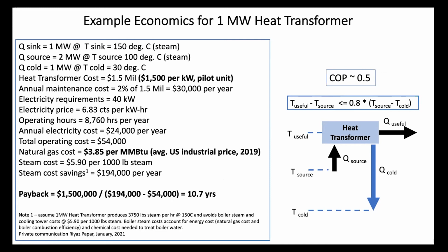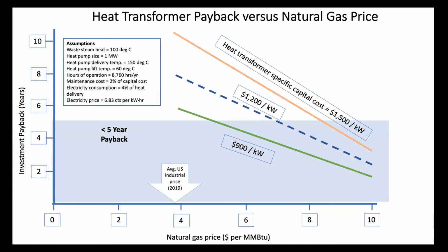So maybe that's not encouraging, but if we go to the next slide — first of all, that $1,500 per kW is for a pilot unit at smaller scale. If we're able to improve the heat transformer technology, reduce cost through heat exchanger innovations and material innovations, and raise the scale of the heat pump above 5 megawatts, and if natural gas prices rise higher than currently, which there's probably a pretty good chance of, we can start to get down to a 2 to 5-year payback region.